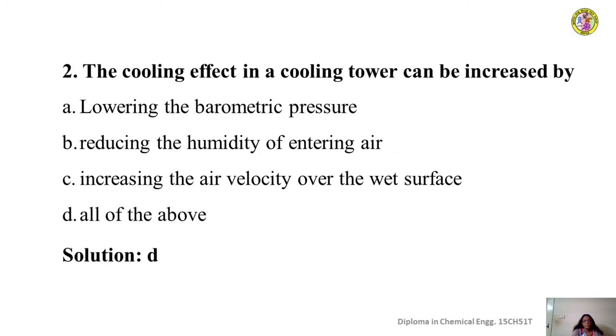So we can increase the cooling effect in a cooling tower by all these methods. We can reduce the barometric pressure, or we can reduce the humidity of the entering air, whereby we can increase the amount of water getting evaporated into the air, and thereby reduce the temperature of the water to still lower values. Then if the air velocity is increased, the cooling effect given to water will also be higher.